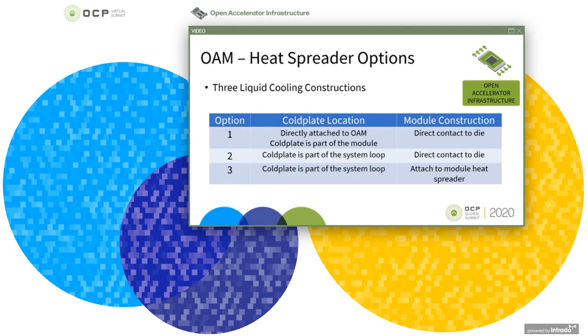The second and third options both have the cold plate as part of the system cooling loop. This eliminates the additional risk of removing and inserting a part of the cooling loop in the field. The second option exposes the OAM die to the cold plate.